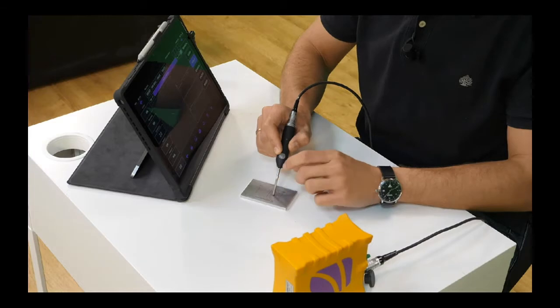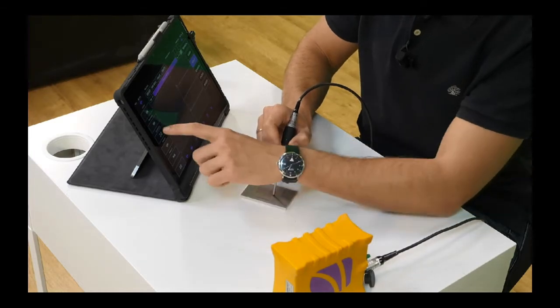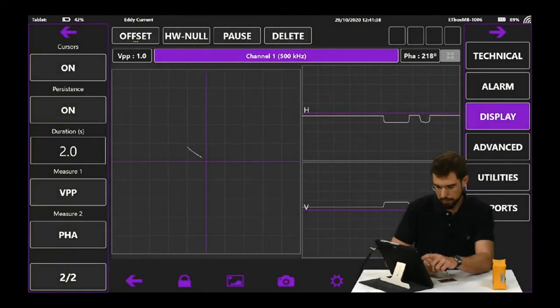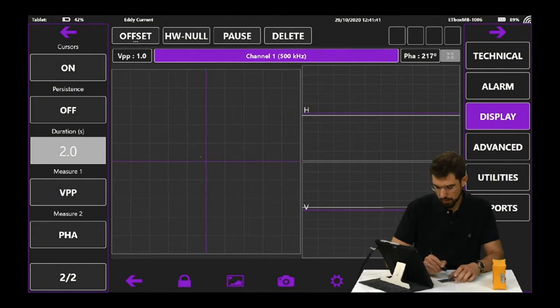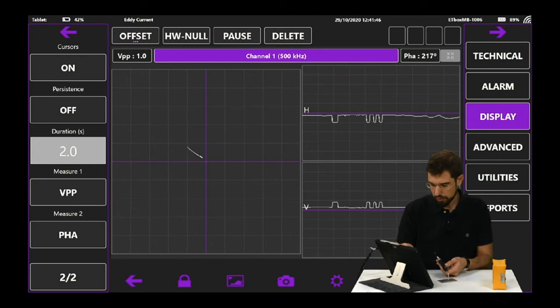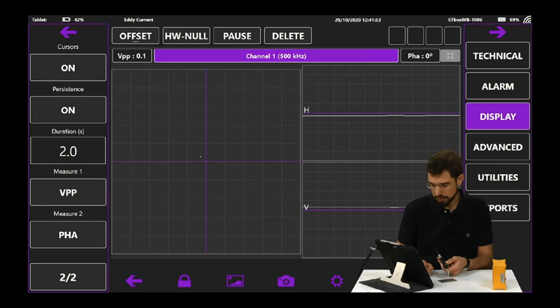The equipment is acquiring, and it's important to take into account that we can turn the persistence mode on or we can turn the persistence mode off. That way, we see that if it's turned off, the whole signal that's acquiring until the buffer is full accumulates on the screen. However, if we turn it on, what we see is that it only represents the 2 seconds that we have configured.